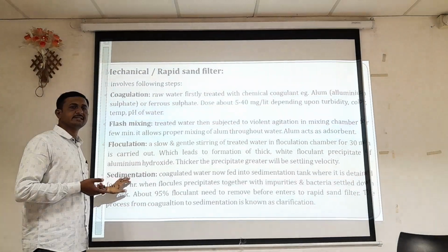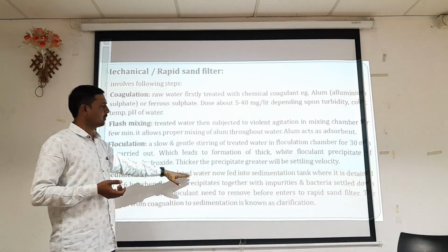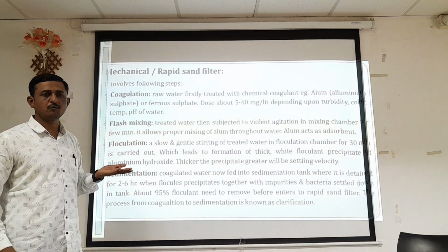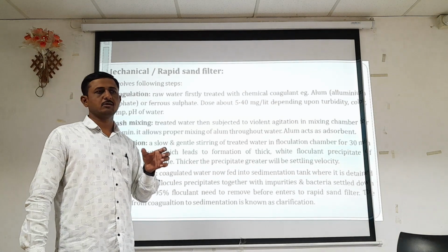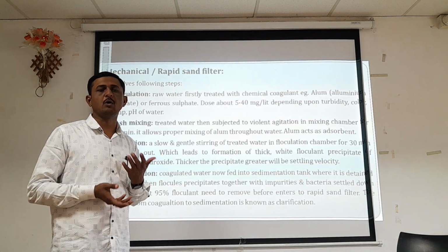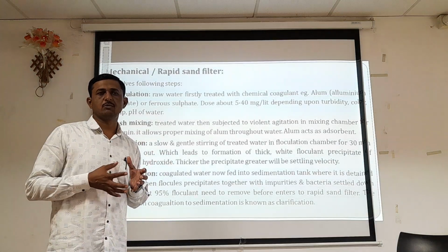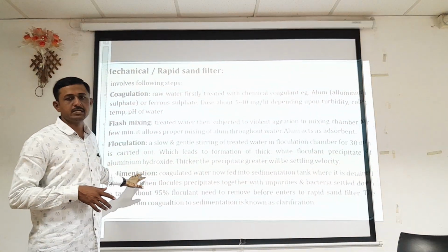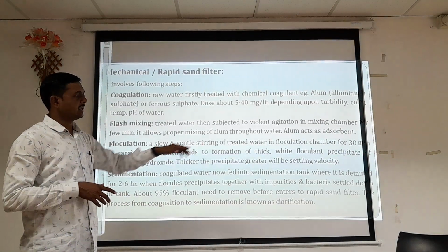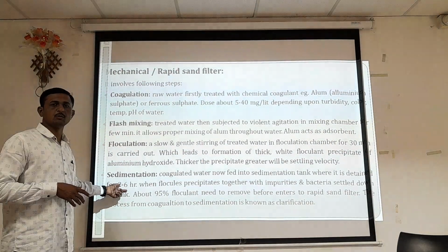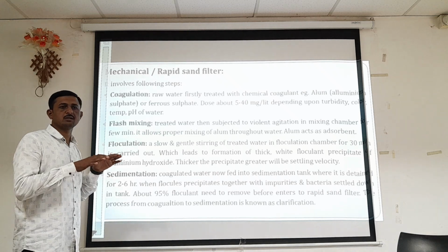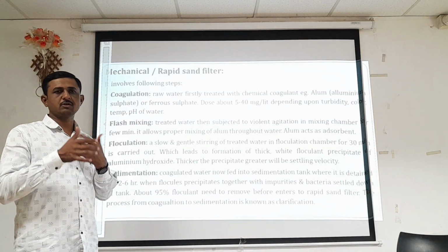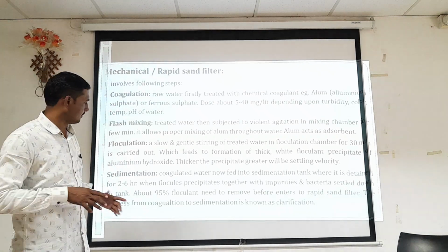Another step is sedimentation. The coagulated water is now fed into a sedimentation tank. It is another tank where the water sample is kept for a few hours, so that the flocs formed in the water easily settle down in the sedimentation tank. Here it is detained for 2 to 6 hours, and no stirring is carried out. That is why the flocs formed in the water settle down properly at the bottom.